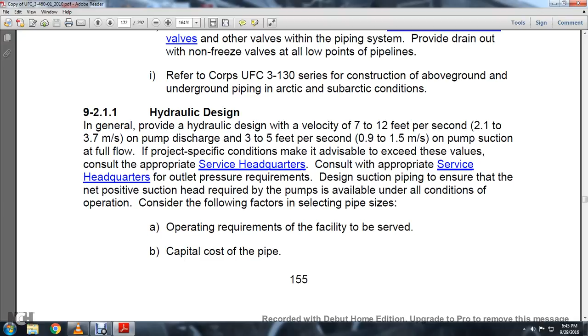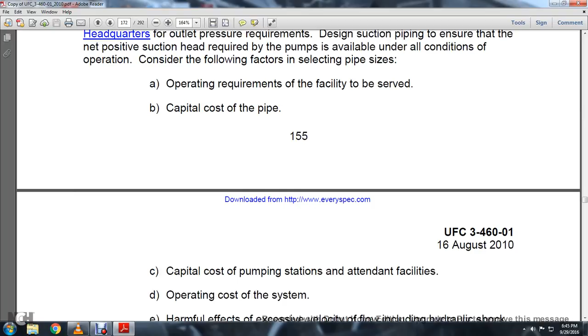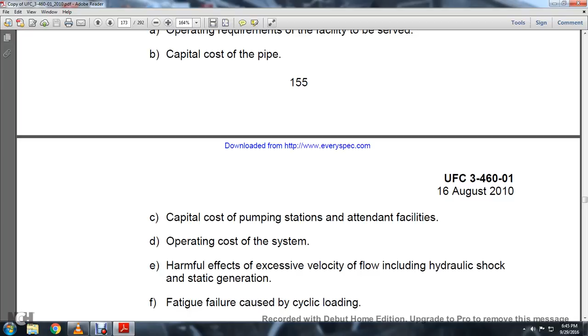Consider the following factors in selecting pipe size or operating requirements for the facility: the capital cost of the pipe, the capital cost of the pumping station and attendant facilities, the operating cost of the system, and the harmful effects of excessive flow velocity, including hydraulic shock, static generation, and fatigue failure caused by cyclical loading.